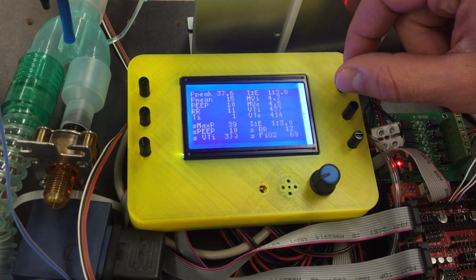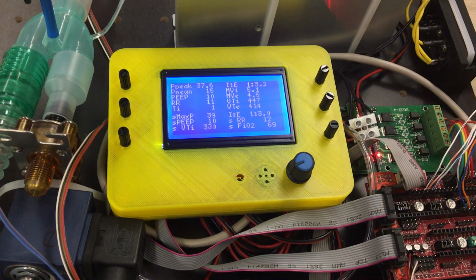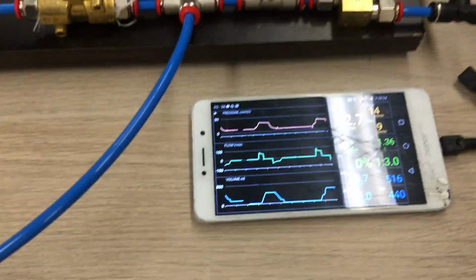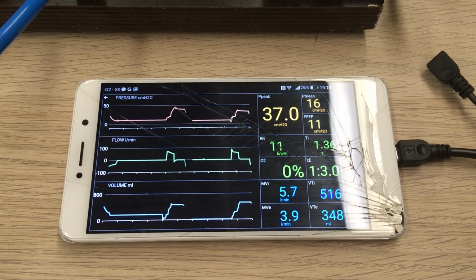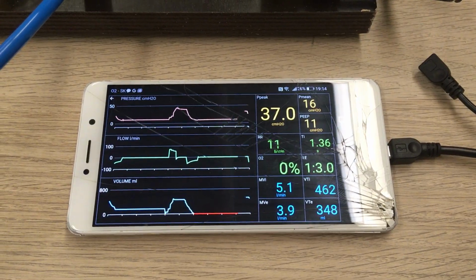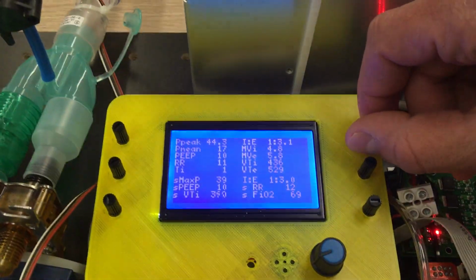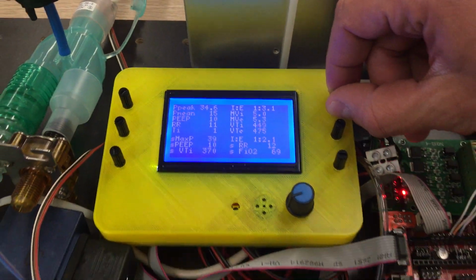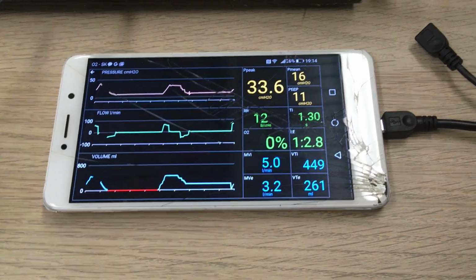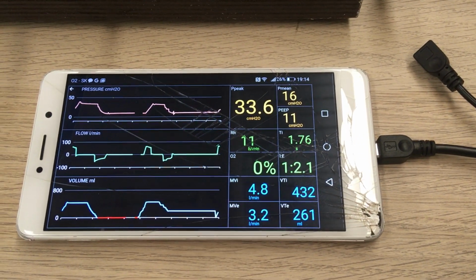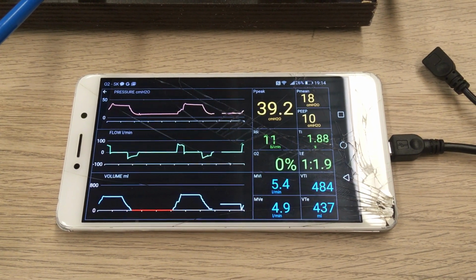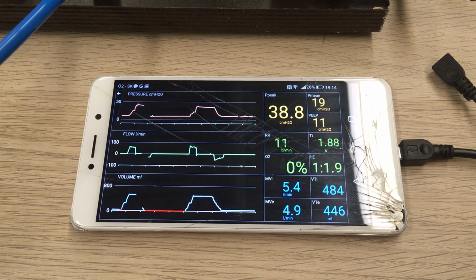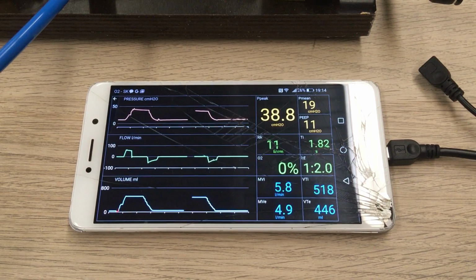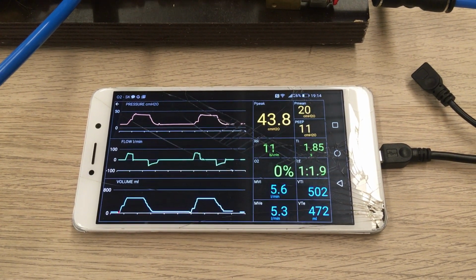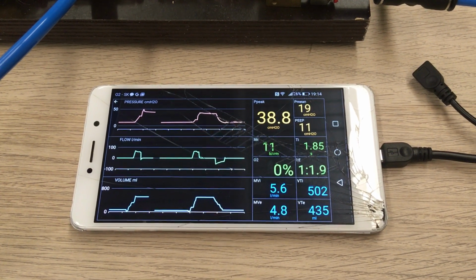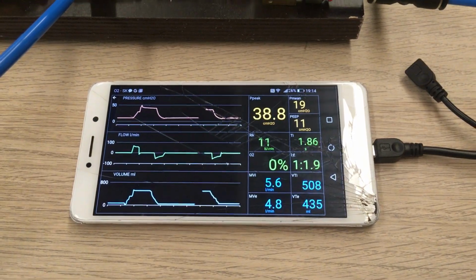We can also change the inspiration to expiration ratio to see what happens, and we can also have a look at the charts of what these changes do to our breathing cycle. So now I will change the inspiration to expiration ratio. It was 1 to 3. Now I will change it to 1 to 2. So the respiration rate shall remain constant, and what happened is the pause after inspiration has prolonged, and the pause after expiration, or the PEEP pause, is shorter now.